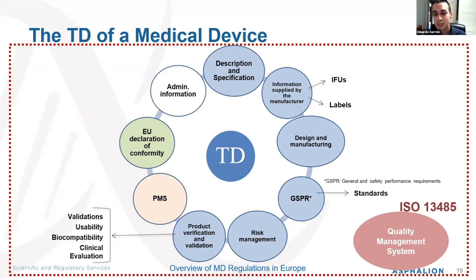You have to include the GSPR checklist. This is mandatory — you've got to include the requirements listed in Annex 1 of the Medical Devices Regulation, and you also have to mention which standards you're following to demonstrate compliance with these requirements.